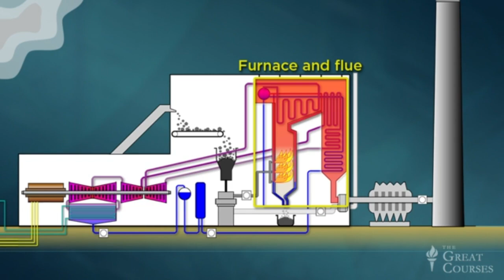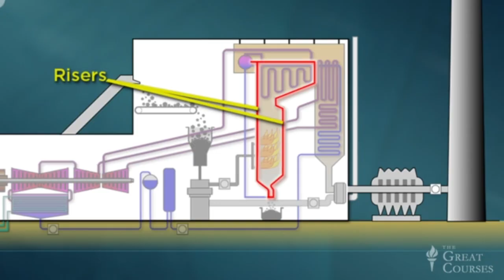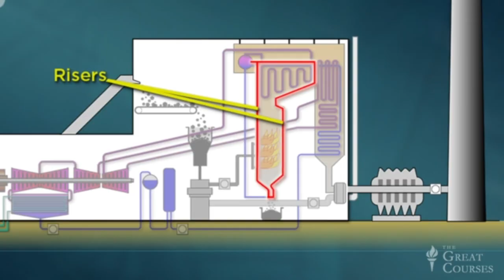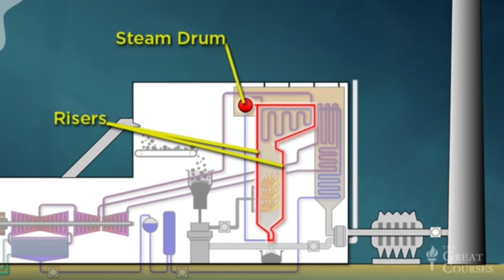The process of heat transfer begins with the boiler, consisting of tightly packed vertical steel tubes called risers, which are actually integrated within the walls of the furnace itself. The risers are filled with water that boils and rises as it's heated by radiant energy from the flames. Each riser is actually part of a closed loop that allows for continuous circulation of this fluid. At the top of the loop is a device called a steam drum, which separates steam from the water.